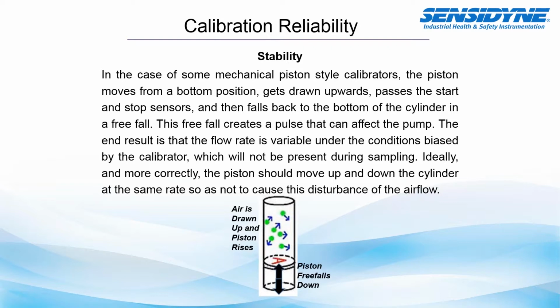Now, in the case of these mechanical pistons, so this would be a dry cylinder where a piston moves up and down through a cylinder. The piston moves from the bottom position. It can get drawn up until it passes the start, and then it'll pass a stop sensor. When it passes the stop sensor, it falls back down to the bottom of the cylinder in a free fall. It's this free fall that can create a pulse that can actually be seen or affect the pump itself. The end result is that the flow rate is variable under the conditions biased by the calibrator, which will not be present when you disconnect the calibrator and the pump is running.